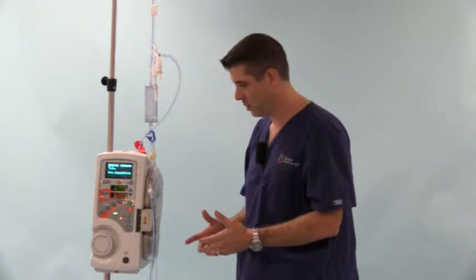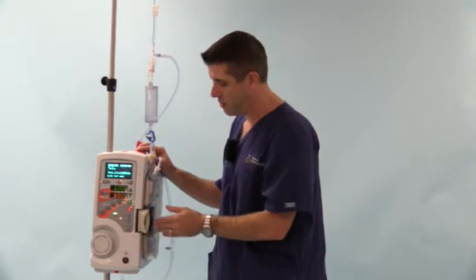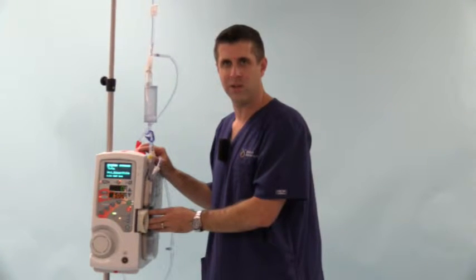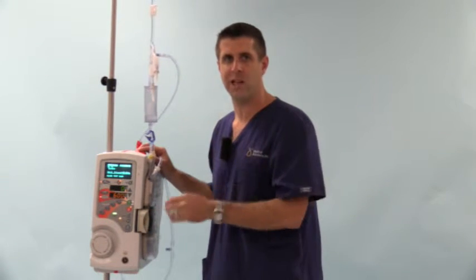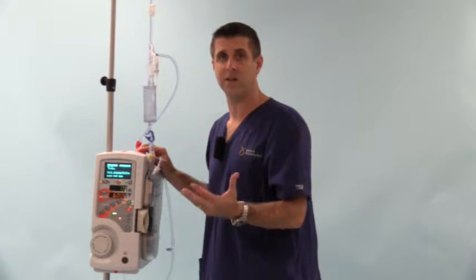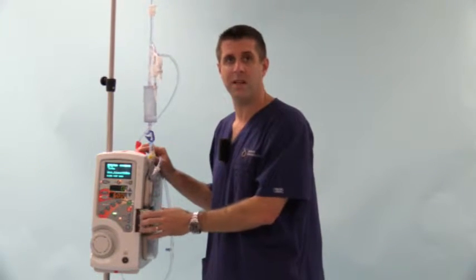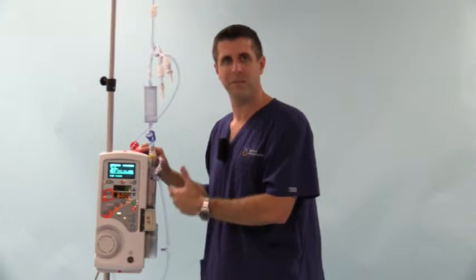The next thing I'd like to talk about is the tubing and the placement of tubing in the door. As you could see, and as we talked about, our system is very easy to set up and can be set up very quickly. But one thing you want to be aware of is that the tubing in the roller pump door is pushed completely in as you're doing your setup. That minimizes the chance that the tubing could become nicked and cause a leak during the case. Typically, if you do see a leak during the case, it's a rare occurrence, but it's usually due to that roller pump tubing being nicked as you put it on the cassette. So something to be cognizant of as you're setting up the equipment.